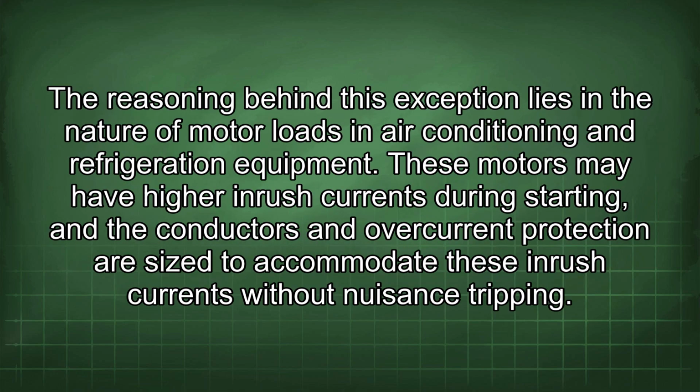The reasoning behind this exception lies in the nature of motor loads in air conditioning and refrigeration equipment. These motors may have higher inrush currents during starting, and the conductors and overcurrent protection are sized to accommodate these inrush currents without nuisance tripping.